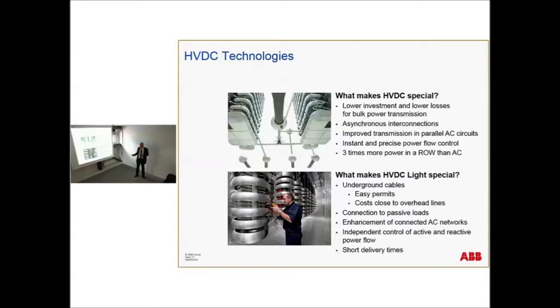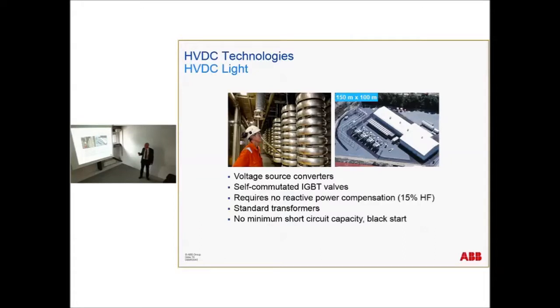If we use the HVDC light, it's a voltage source converter. It doesn't need to have any short circuit power to commutate and to work. It can also use these XLPE cables, where the weight is almost only half compared to a conventional mass impregnated cable with the same cross-section area. It can be connected to radial networks and passive loads. We control the power, even reactive power. And the size is considerably smaller compared to the HVDC classic for the same power rating.